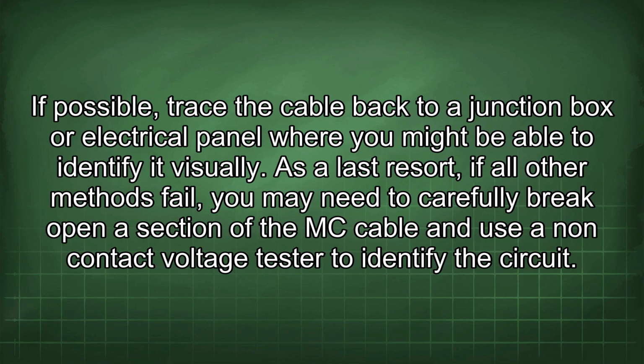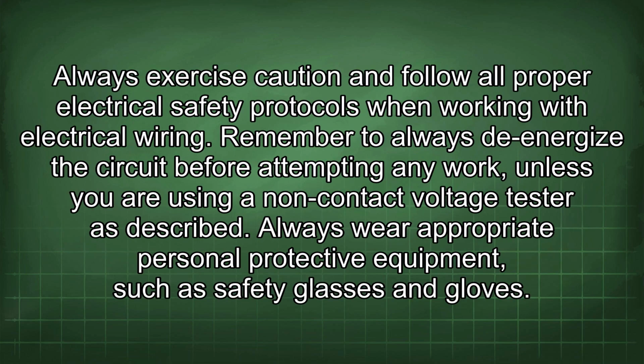As a last resort, if all other methods fail, you may need to carefully break open a section of the MC cable and use a non-contact voltage tester to identify the circuit. Always exercise caution and follow all proper electrical safety protocols when working with electrical wiring. Remember to always de-energize the circuit before attempting any work, unless you are using a non-contact voltage tester as described.